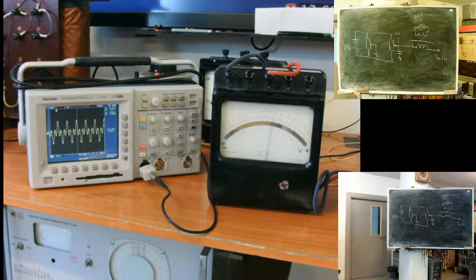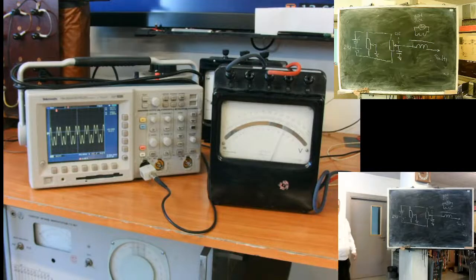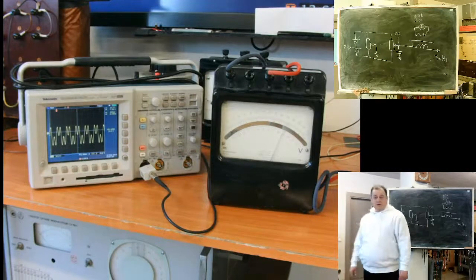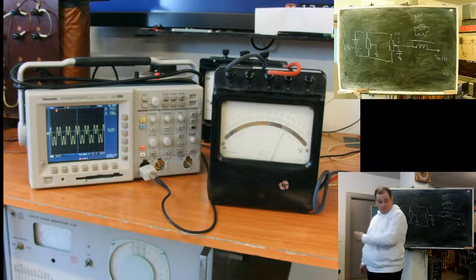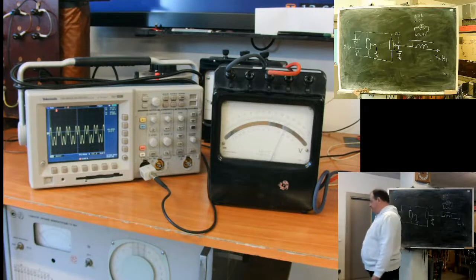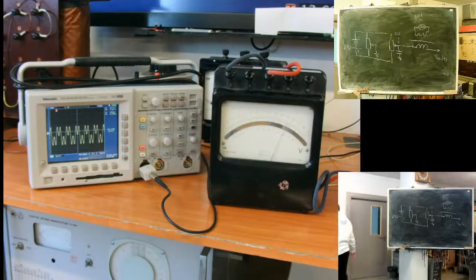In the worst case scenario, it's 17. This one should be 20, it's 20. Should be 24, it's 22. Should be 23.5, it's 22.5. So we see an error - not fantastic, but we see a difference, 3 volts from 20.